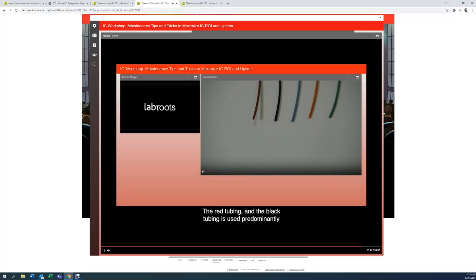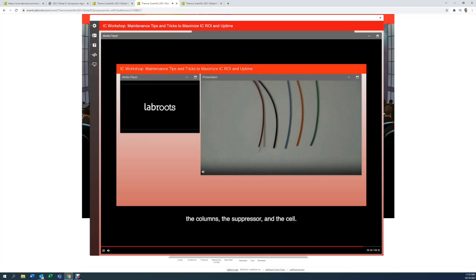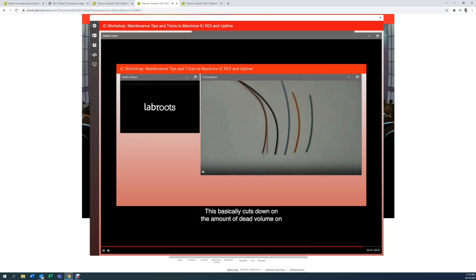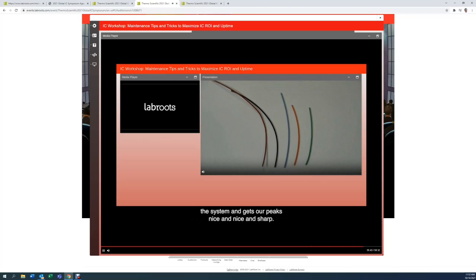The red tubing and the black tubing is used predominantly for the chromatography side of the instrument, which is basically anything after the load injection valve. So anything between the load injection valve, the columns, the suppressor, and the cell. This basically cuts down on the amount of dead volume on the system and gets our peaks nice and sharp. So that's 5/1000th of an inch and 10/1000th of an inch.